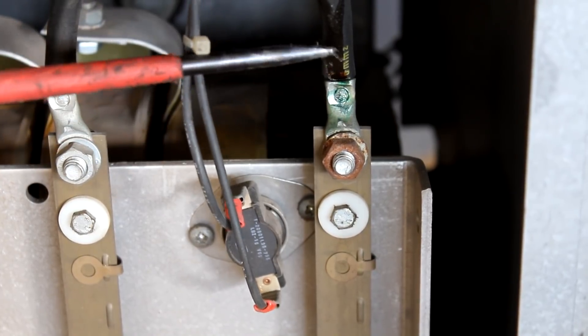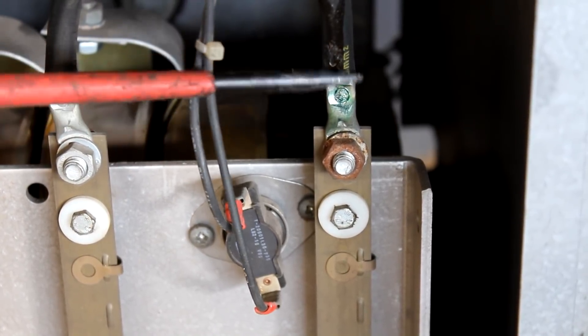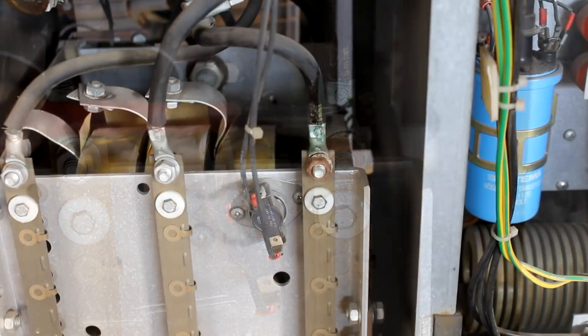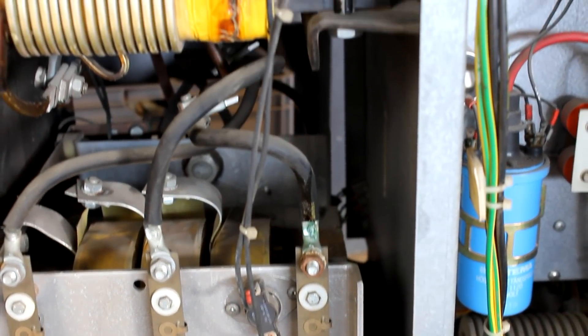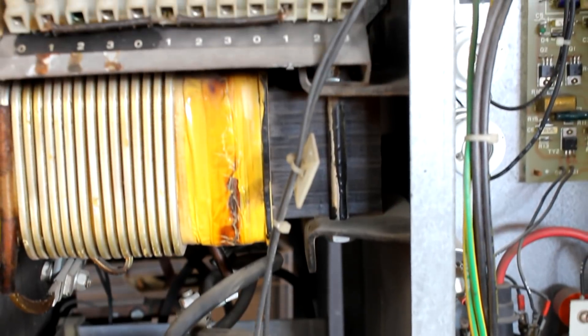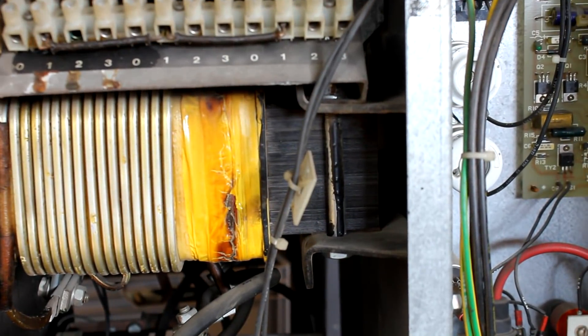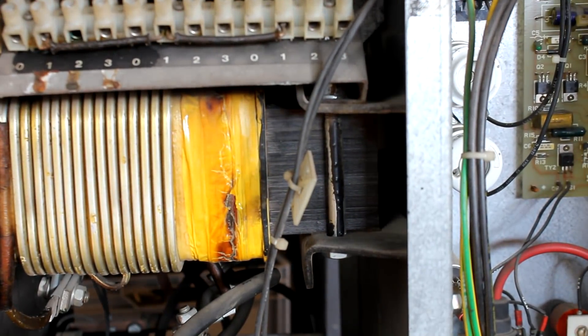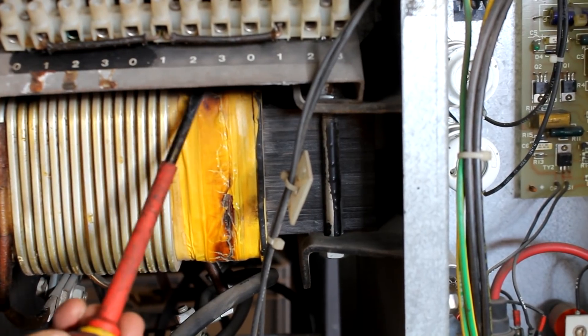Not quite sure why that happened. And up here, and much more importantly, we can see that the transformer is obviously damaged. One of the windings, at least, had to be overheated at some point for this to happen. I mean, you need a certain temperature for this kind of tape to literally burn through.